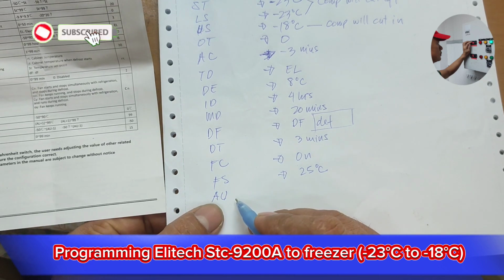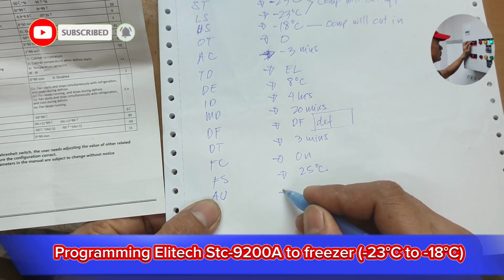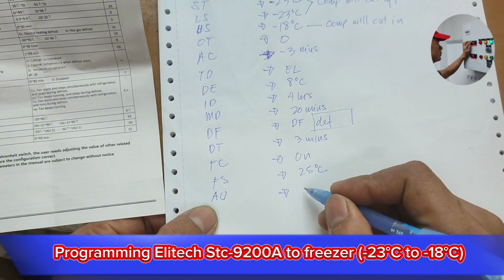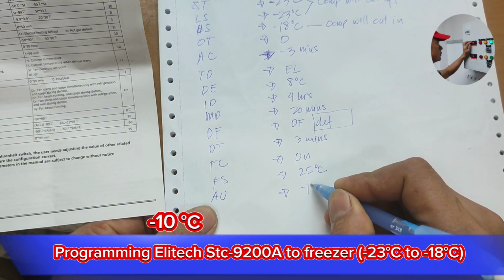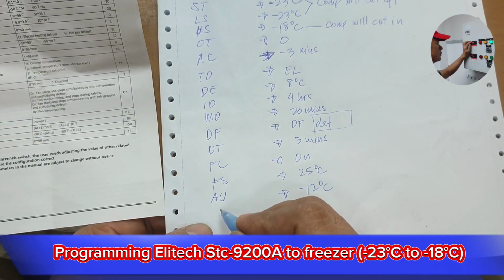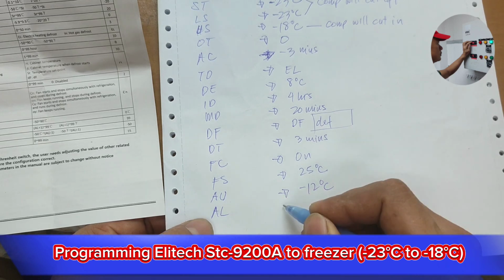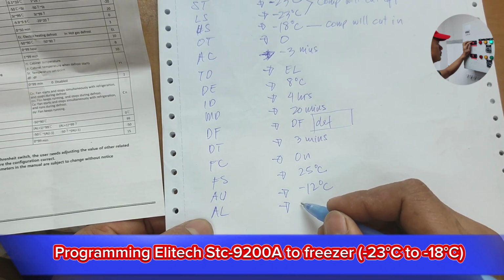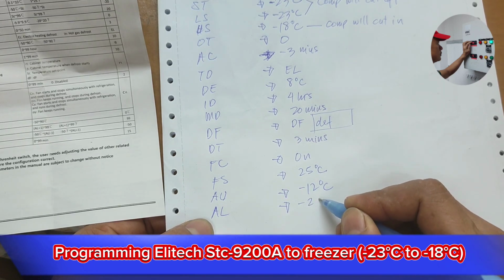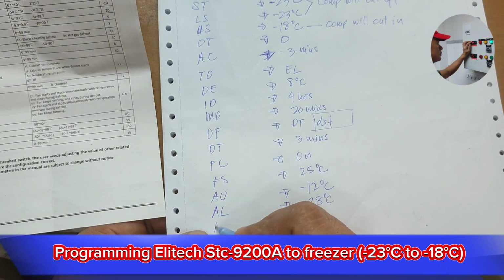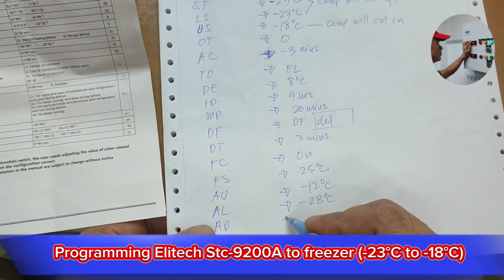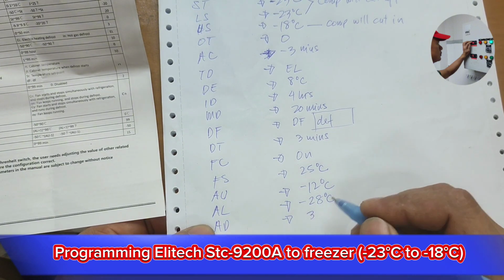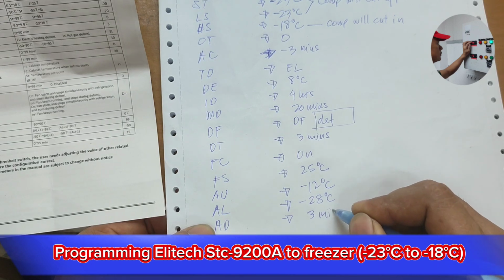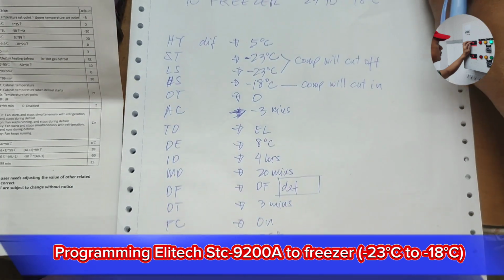AU, this is the high temperature alarm, we set that to negative 12 degrees Celsius, and the AL, the lower temperature alarm, we set that to negative 28 degrees Celsius, and we delay the activation of that to 3 minutes. So that's all.